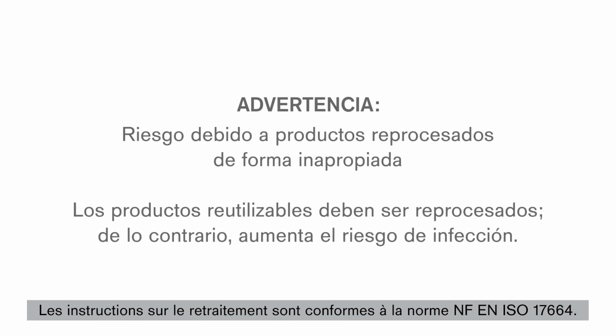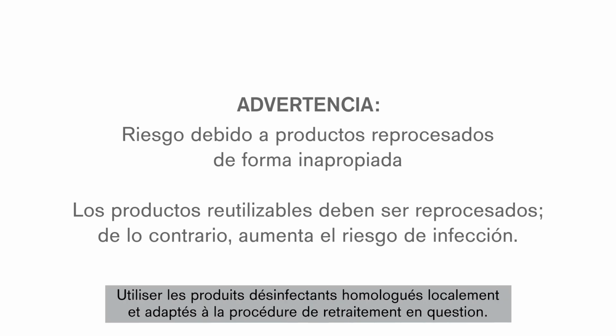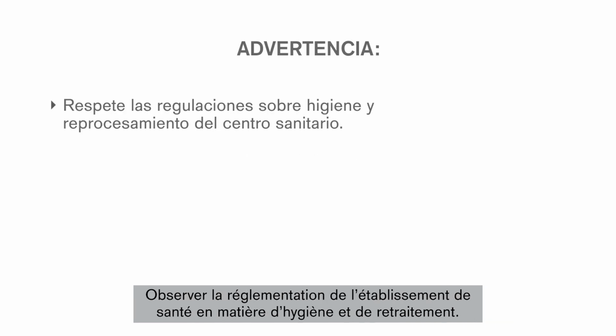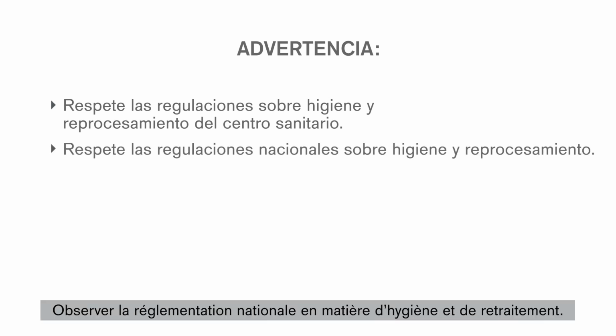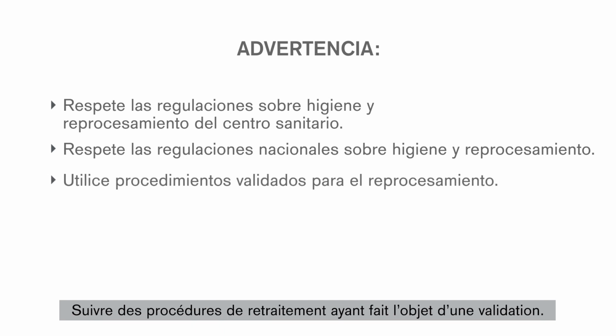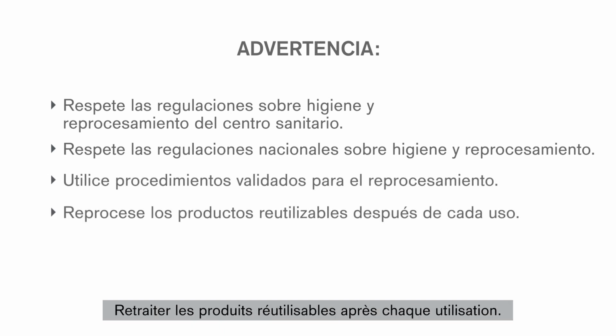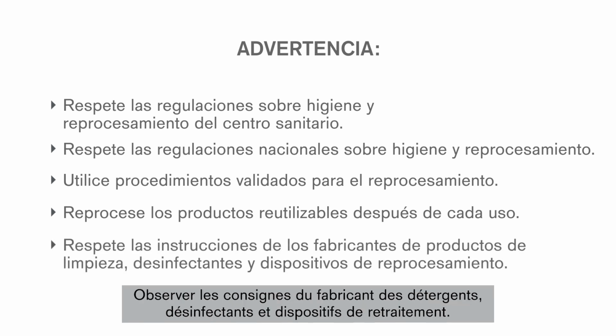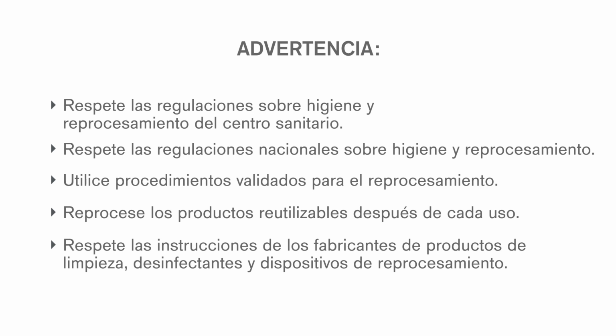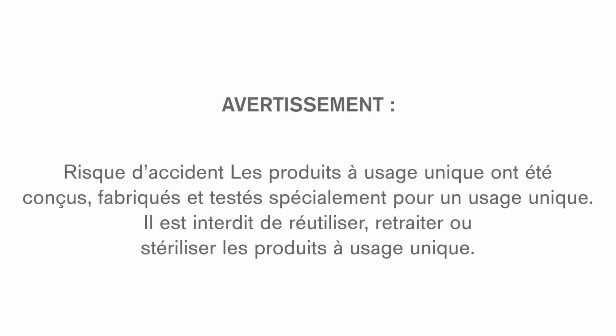The instructions for reprocessing meet the requirements of ISO 17664. Use disinfectants that are nationally approved and are suitable for the respective reprocessing procedure. Observe the hygiene regulations and reprocessing regulations of the healthcare facility. Observe national hygiene regulations and reprocessing regulations. Use validated procedures for reprocessing. Reprocess reusable products after every use. Observe the manufacturer's instructions for cleaning agents, disinfectants, and reprocessing devices.